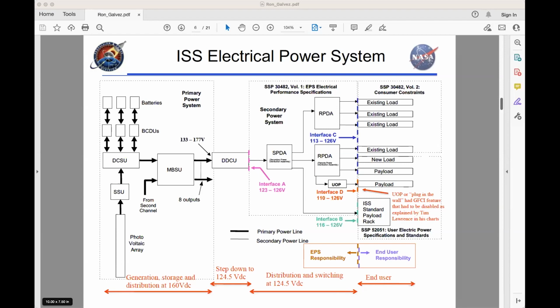We had a gate oxide issue with one of the FETs, which ended up fooling the RPC, the electronic switch, into thinking it was in current limiting, so it just tripped off. Out of nowhere, a load loses power, with no overcurrent or indication of anything other than it just stopped working.